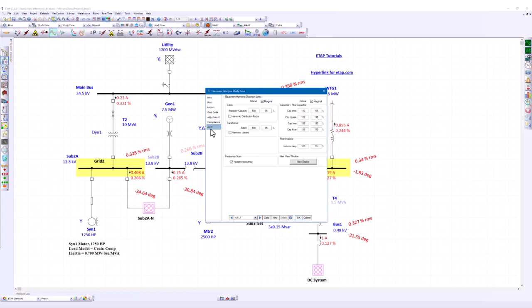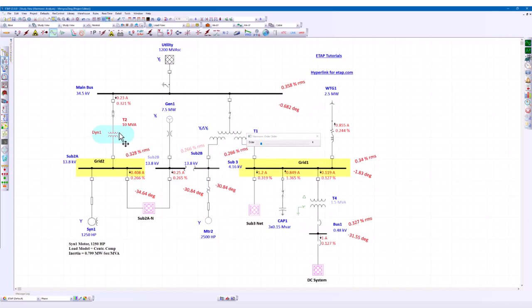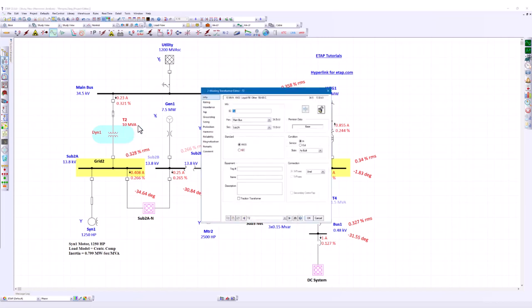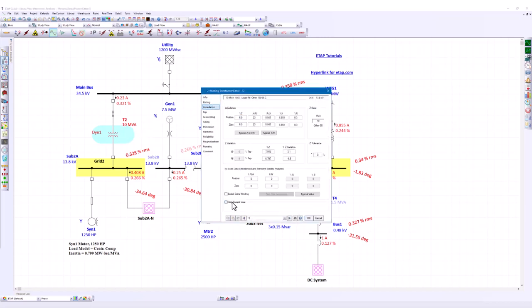We can evaluate cable ampacity by considering the harmonic distribution factor. And also, you can consider the transformer derating by using eddy current losses. The transformer eddy current losses can be defined in the transformer editor impedance page.